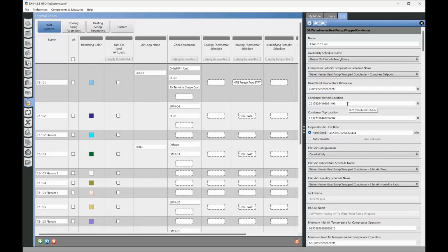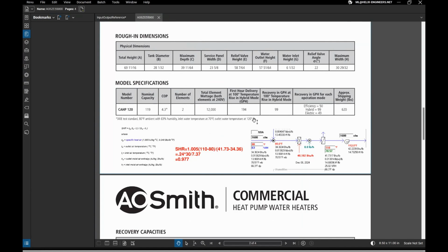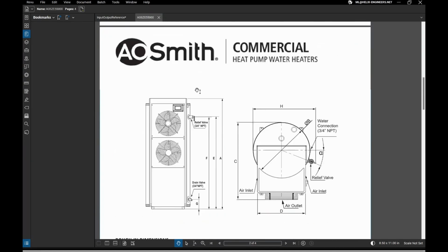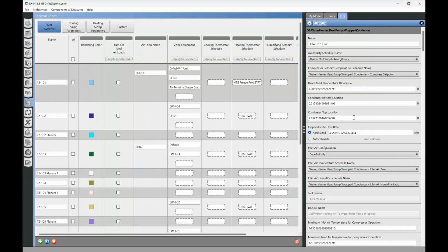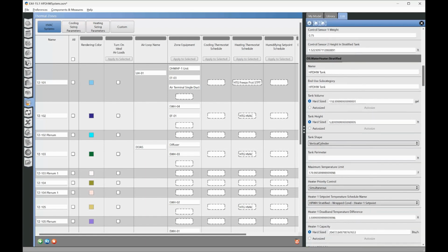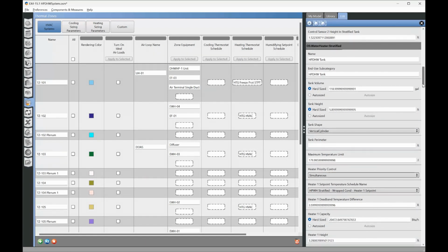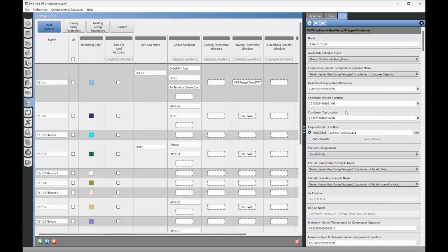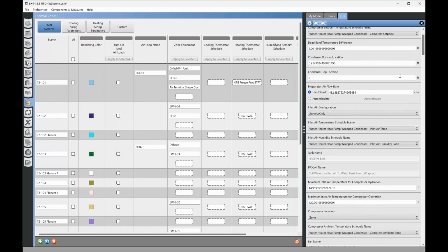Condenser bottom location and top location. So I'm not entirely sure what these are used for, but that would be basically these dimensions here. We have the compressor that basically takes up the full height of the tank. So condenser top location, bottom location. We can look at the size of our tank. The height of our tank is 5.89 feet. So for our condenser bottom and condenser top, we'll just put like, I don't know, 5 feet here. So that should give us those dimensions there.